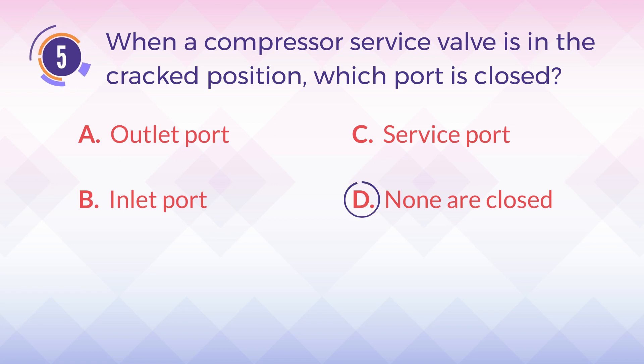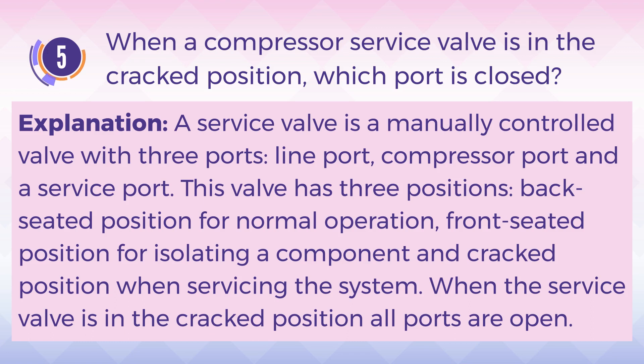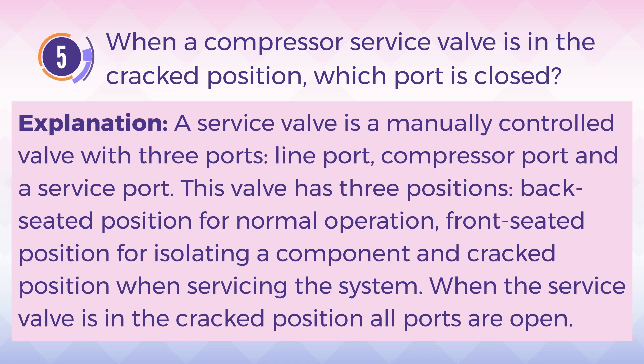The answer is D, none are closed. A service valve is a manually controlled valve with three ports: line port, compressor port, and service port. This valve has three positions: back-seated position for normal operation, front-seated position for isolating a component, and cracked position when servicing the system. When the service valve is in the cracked position, all ports are open.